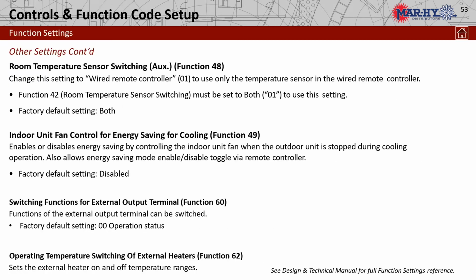Okay, 48, room temperature sensor switching. We actually went ahead on function 42 and switched to 1. 1 means we're using both the indoor and the thermostat sensors. In function 48, we can just pick the sensor in the thermostat. But you got to set 42 to both so that you can go to function 48 to set it to just the remote controller. So there is some wildness to their madness here, but that's how this will go.